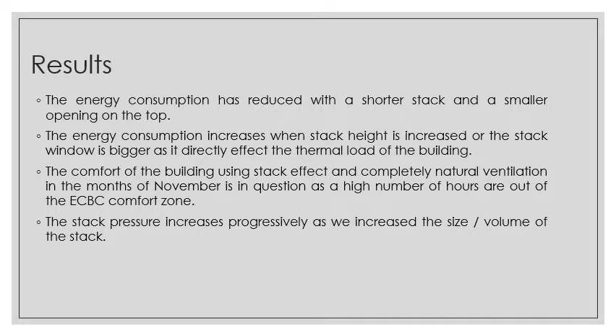The stack pressure increases progressively as we increase the size volume of the stack. And finally, a total savings of 10% was simulated with a short and wide stack with a small window opening on the top. The savings was due to reduced thermal load of the building and no HVAC requirements for 2 months of the year.